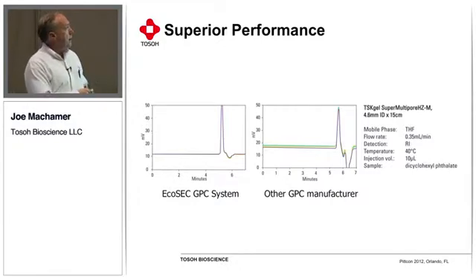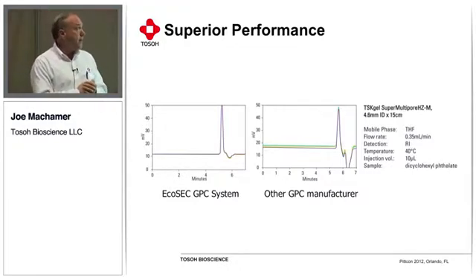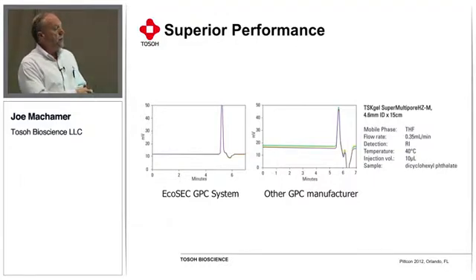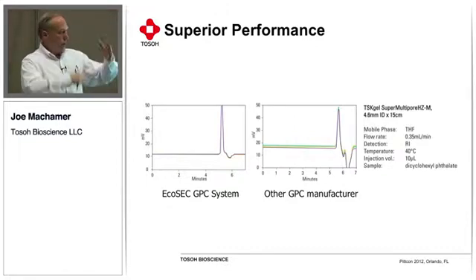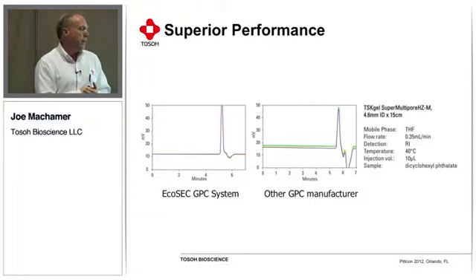Another feature of the instrument is the dual flow refractive index detector, and what that provides is superior performance in terms of baseline stability. What we're showing here are chromatograms where we're running the same column, samples, mobile phase, etc., but on 2 different systems. We're overlaying 5 chromatograms on the EcoSEC GPC system, and you can see that there's virtually complete overlap. There's really no drifting or no difference between any of these individual injections. However, when that same sample is run on a conventional refractive index detector, you can see how the peaks are offset from one another, and that's going to lead to inaccurate data.